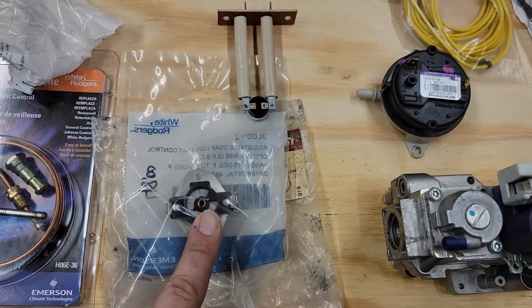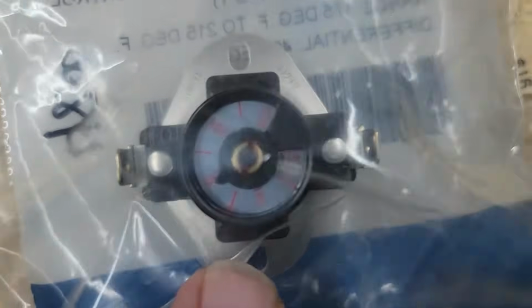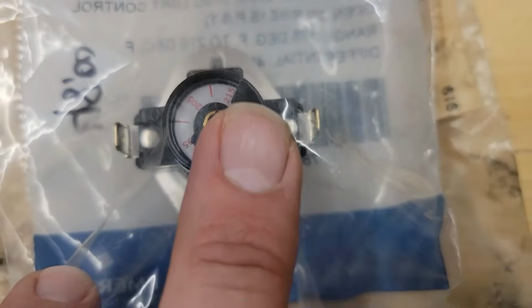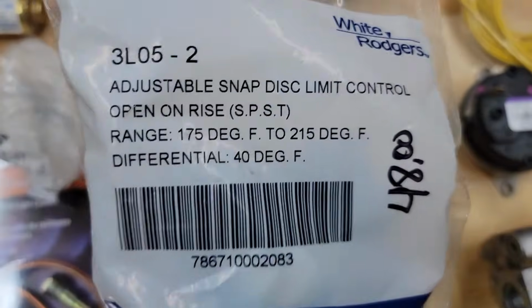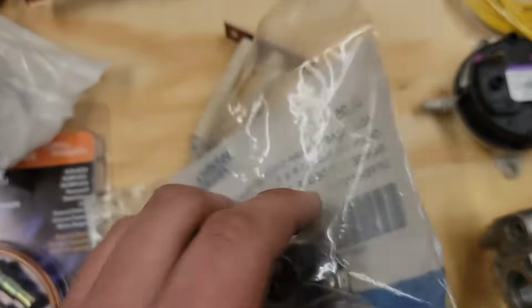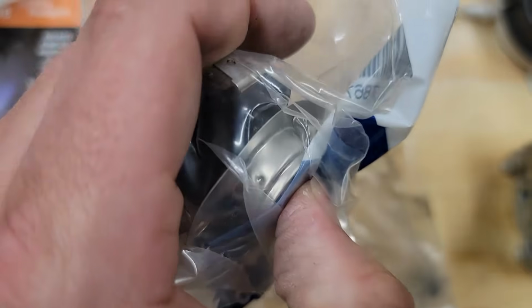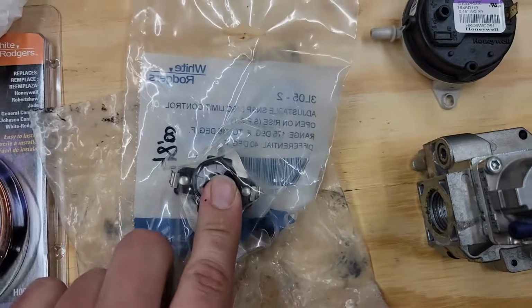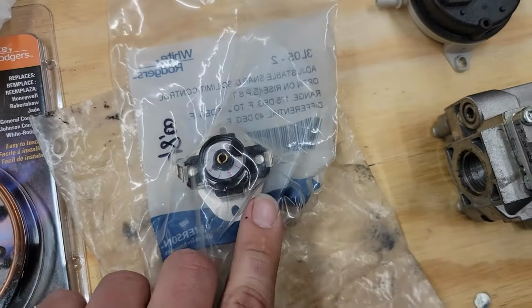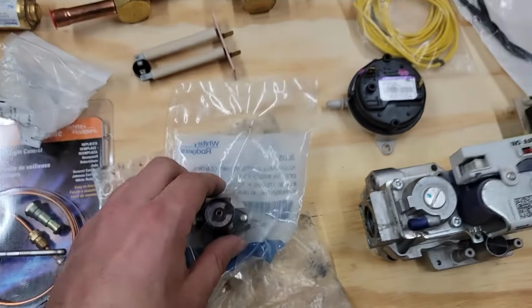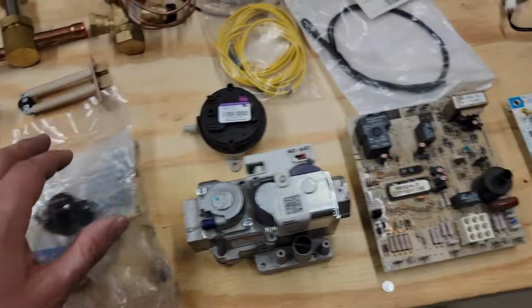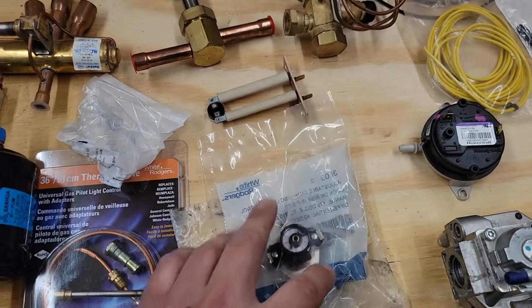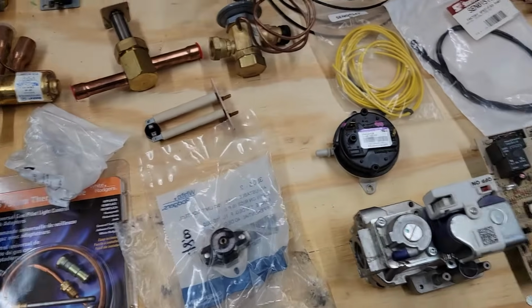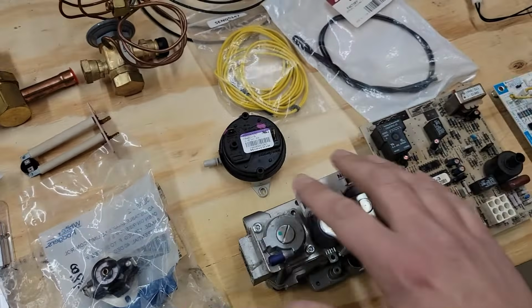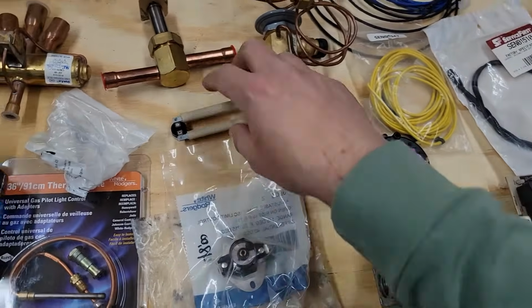And this is a limit switch, okay, and these are found in furnaces. This is an adjustable limit switch, so it goes from 175 up to 215. And it says right here, it's a snap disc limit control. What does that mean? Well, when it gets hot, it pops this disc on the bottom, okay? And usually that will open this up. So you'll no longer have a circuit through this limit switch. It'll be open, and that will usually shut down the ignition. And sometimes it makes your blower run so that your limit problem, or your hot situation where it's too hot, that ends because it cools it down.